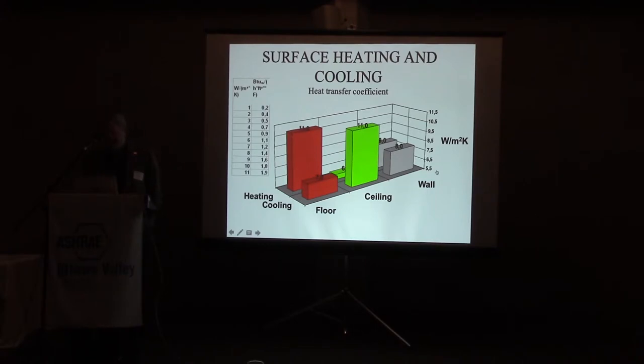If you have a ceiling, if you have a floor, if you have a wall, the convective part changes. If you have a warm floor, the air will get a little warmer around the floor and it will rise, warm air rises, so you have a significant amount of convection also from a heated floor. But if you have a cool floor, you don't have this convection. So out of the 7 watts per square meter per degree heat exchange coefficient, about 80%, 5.5, is radiation.